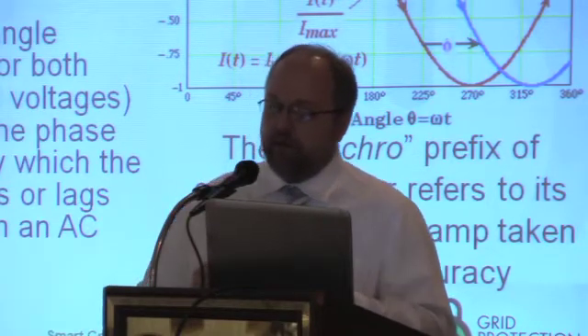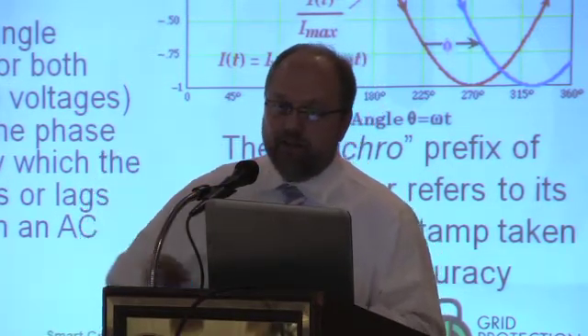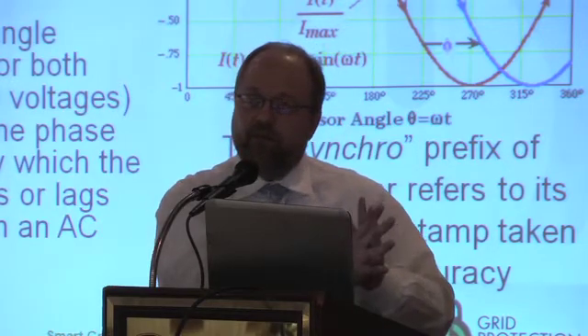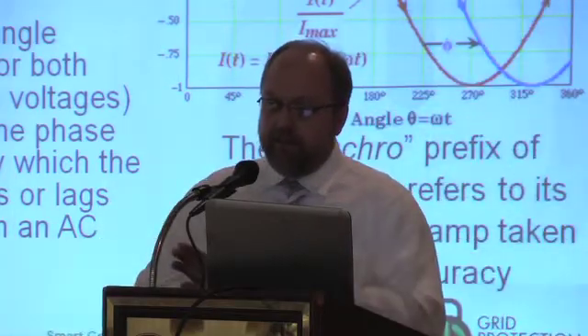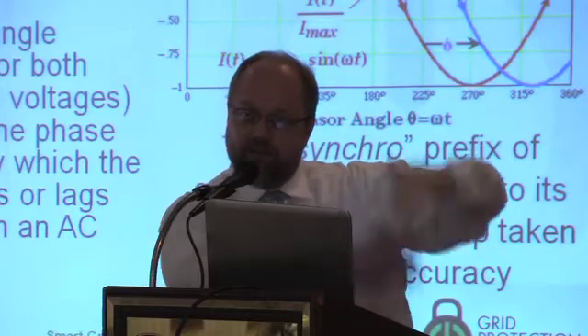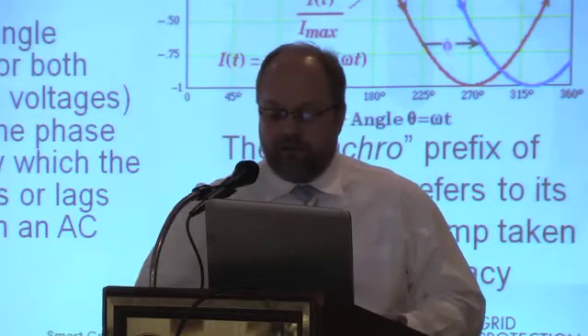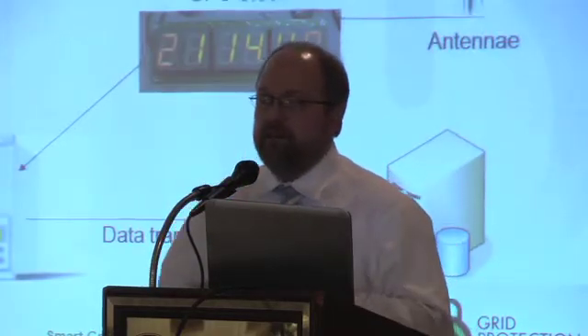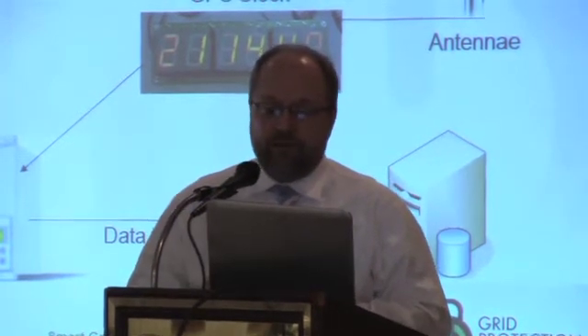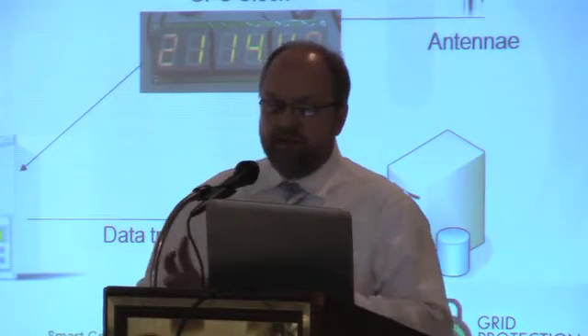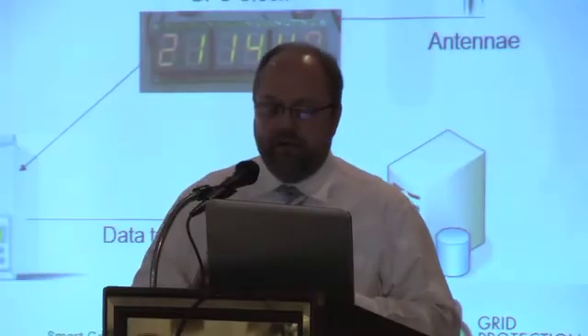The synchro part of the phasor comes from a timestamp that gets collected right when the item gets measured. The time synchronicity of the measurements is what makes this special, because there are network delays. If you're able to figure out exactly when everything was measured and line them up, you get an idea of what's going on on the grid. There are devices in the field today — and there are several DOE grants to install lots of them. They're called phasor measurement units. These devices measure phasors at a very high frequency and push the data back to control centers at about 30 samples a second.